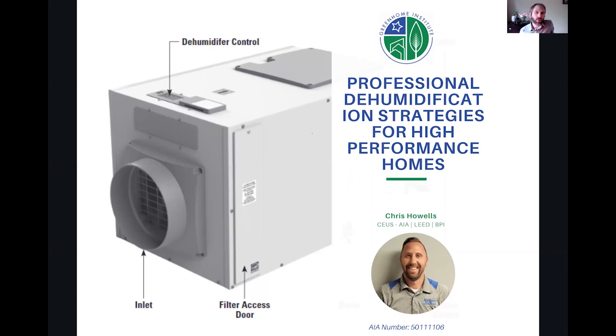So I wanted to go back to one thing you were just saying, since you touched on the question about upgrading the filter. I wanted to expand on that, because in some instances you showed the ventilating dehumidifier added on the return side and sometimes on the supply side. On the return side, there's a concern about pulling in PM 2.5 during outdoor air events, which we can anticipate occurring more often, so having a beefier MERV 13 or 16 filter probably helps. But is there a downside to having all this filtration when you're trying to bring in that fresh dehumidified air? If not, why not just put it in the return and not the supply?